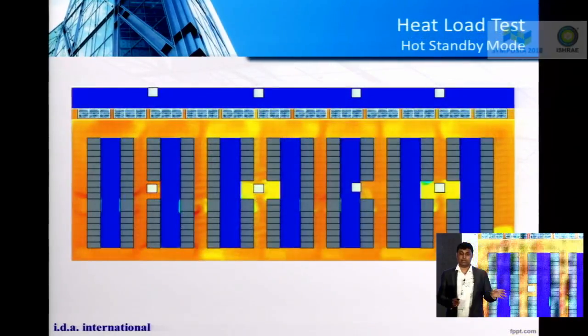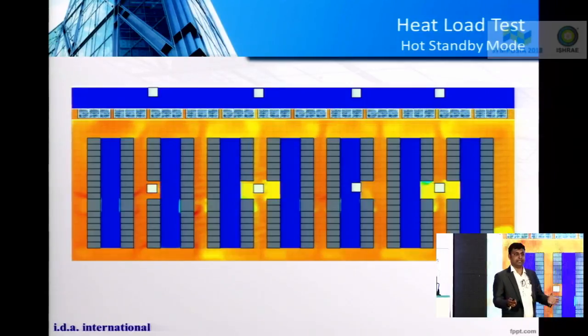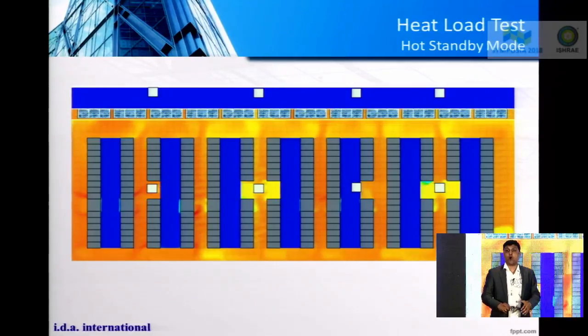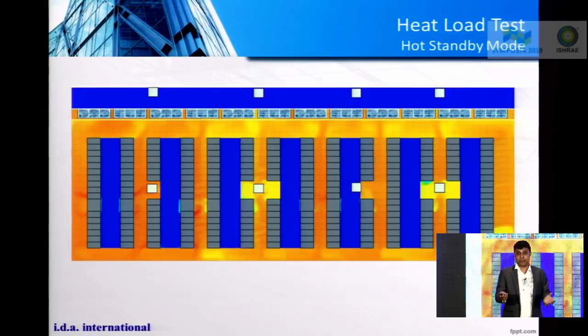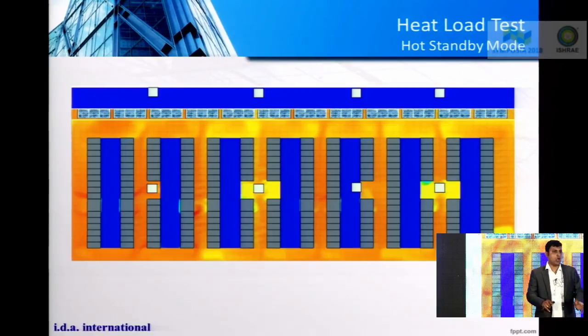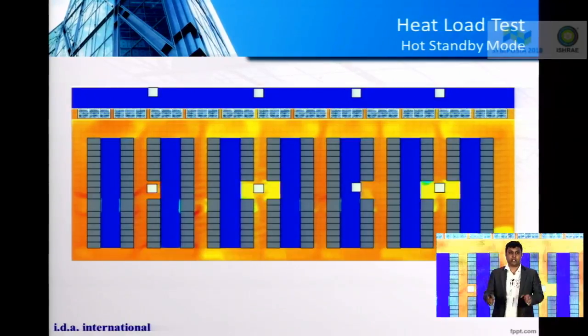The first test, the way I have to proceed, is I can start with the hot standby mode. A hot standby mode means that, whether you design it in N+1 configuration or in N+2 configuration, all the CRAC units are running.